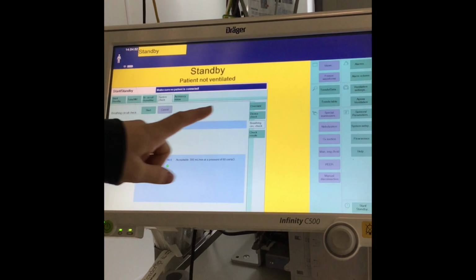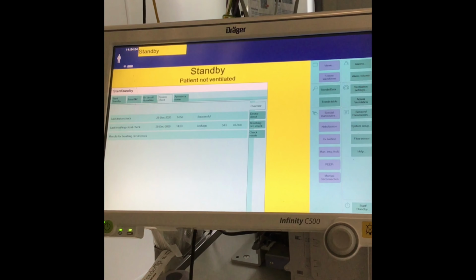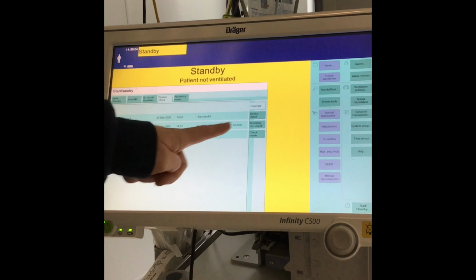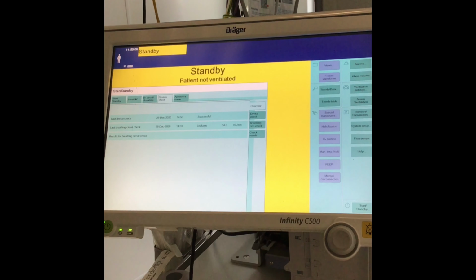If you go on to the overview here, you'll see that the last device check was completed on today's date and at the same time, and that it was successful. And the last breathing circuit check, also the time and date and the leakage that was within the ventilator tubing.